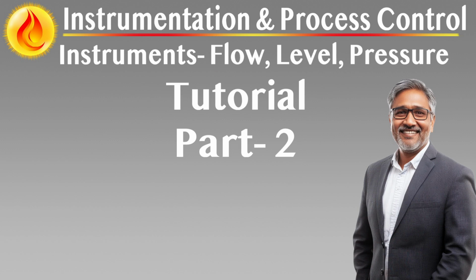Material selection strategy to match process severity and corrosion risk. Instrument materials must be selected with the same rigor as process piping and equipment, ensuring compatibility with fluid chemistry, mechanical stress, temperature, cycling, and environmental exposure. Selection begins with the baseline assumption of AISI 316L stainless steel for all wetted components in clean or mildly corrosive services. However, this general standard is not universally suitable and must be reevaluated for each application based on actual fluid behavior and long-term exposure. For systems with chloride-bearing water in carbon steel lines, 316L may be subject to pitting or stress corrosion cracking, particularly under stagnant or warm conditions.